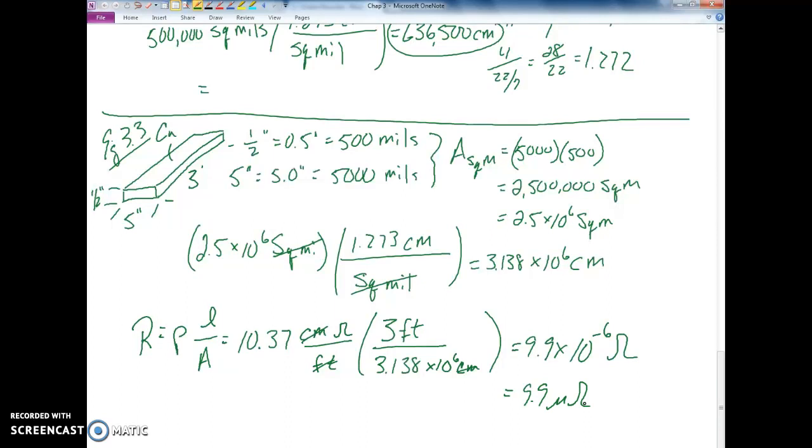And there are actually devices out there called micro-ohmmeters that you can measure that resistance with. In my line of work, doing maintenance on switchgear in the past, that's a test that you actually do. It's a good way to test connections, predominantly, is how you do it. But in this case, it'd be a good example of actually measuring that resistance of that piece of bus.